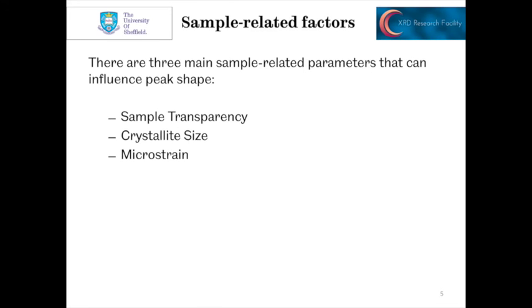There are three main sample-related factors, and obviously these are going to vary much more from sample to sample that goes into the machine. The three main effects are sample transparency, crystallite size, and microstrain. We'll look at each of these in turn.